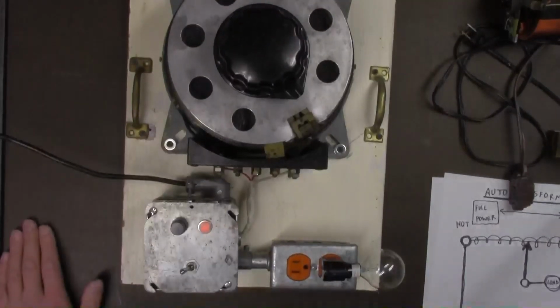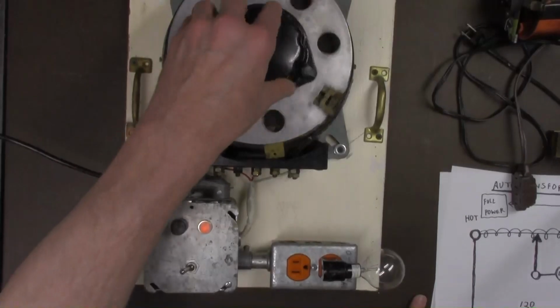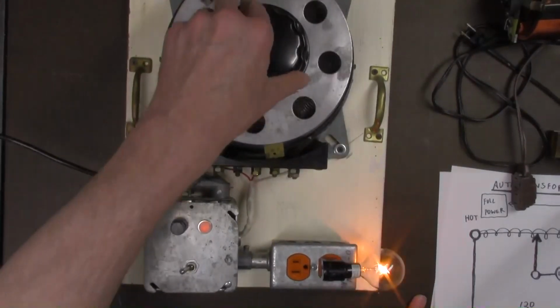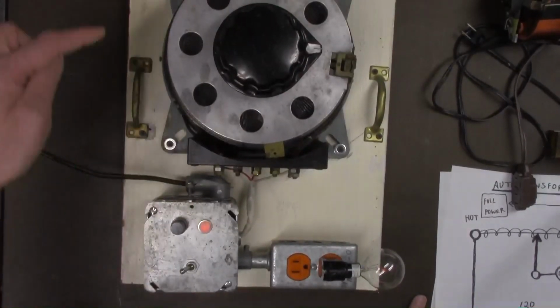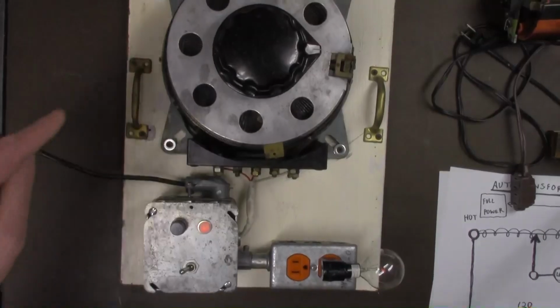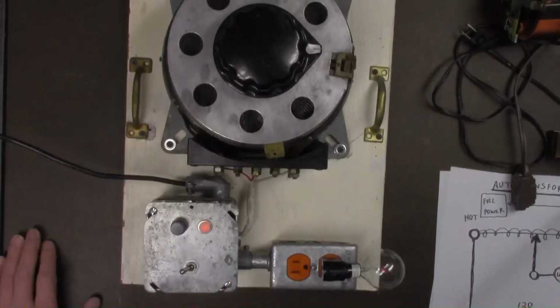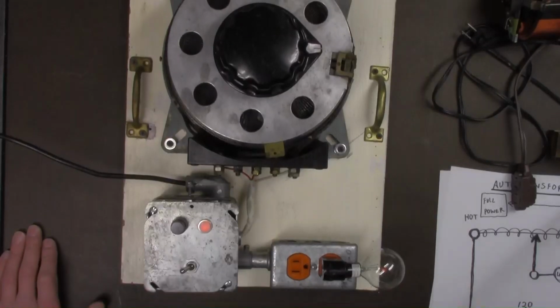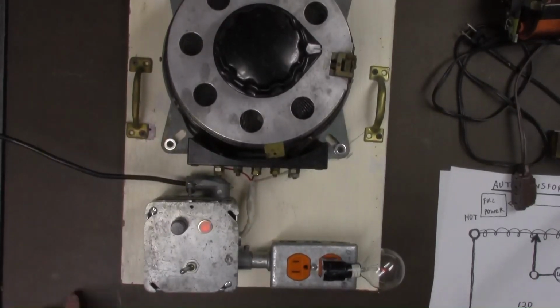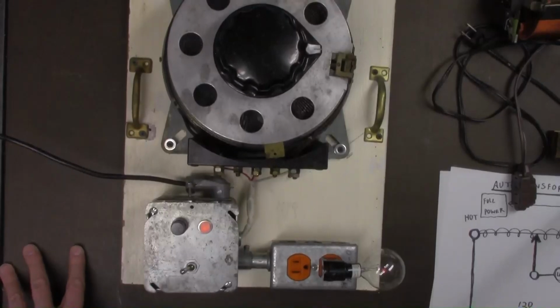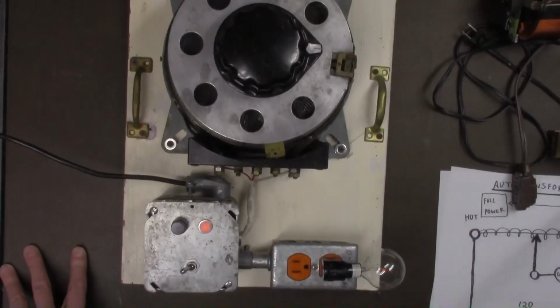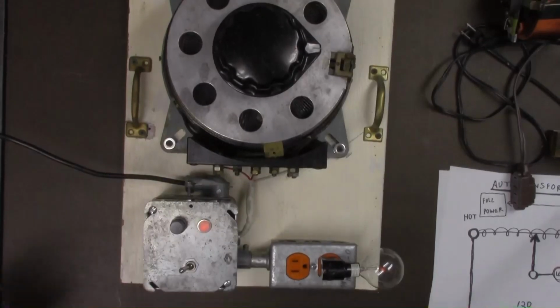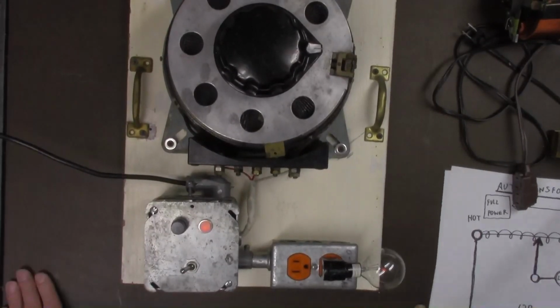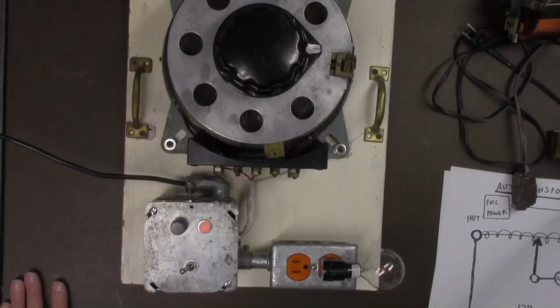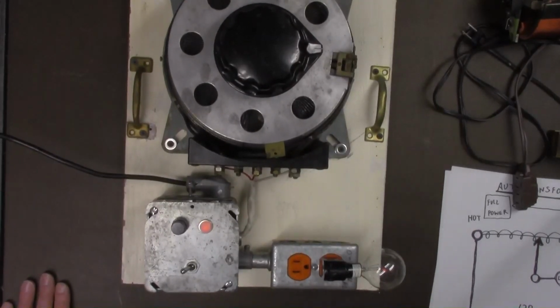Safety considerations for the auto transformer: the cover has been removed here for illustration purposes, but if you touch any part of the coil, it's at full power, so you don't want to come in contact with any electrified parts. Depending on how it's wired, it could be 240 volts, depending on the type of auto transformer. So if you come in contact with one of these things, be very careful—you could be electrocuted to death.